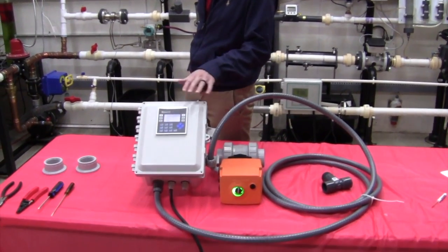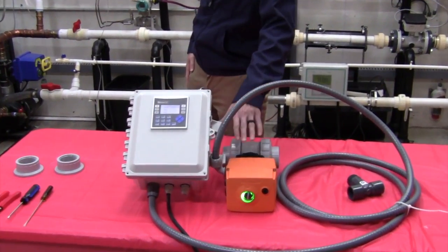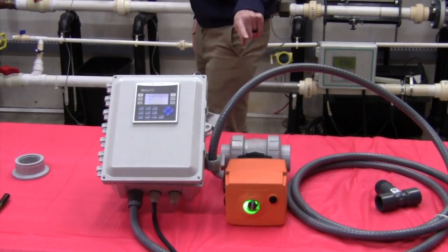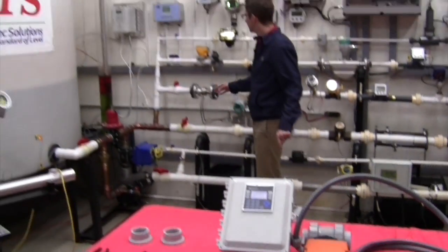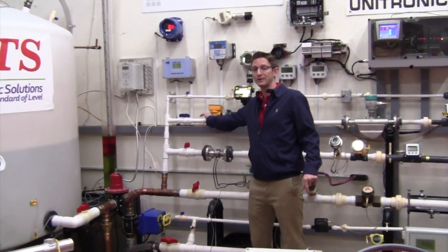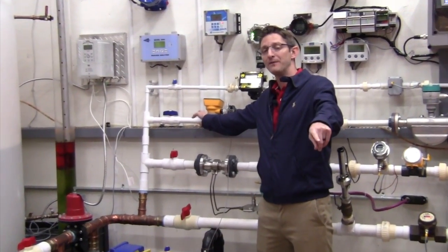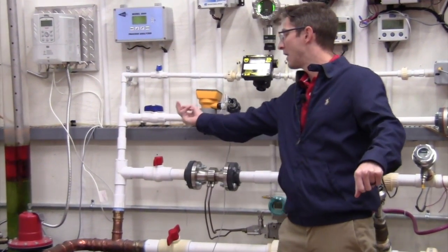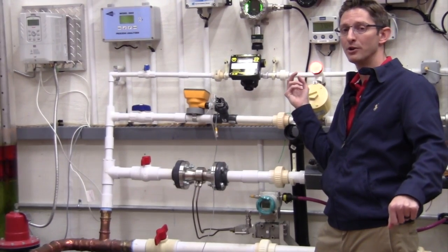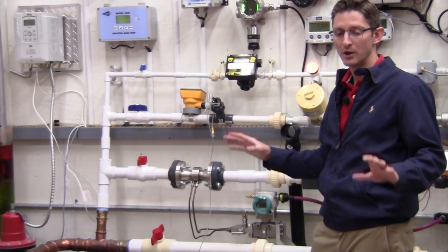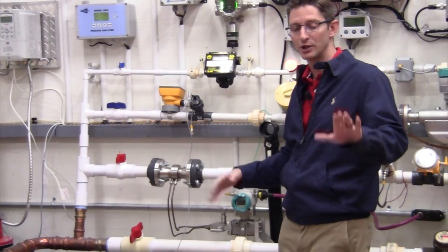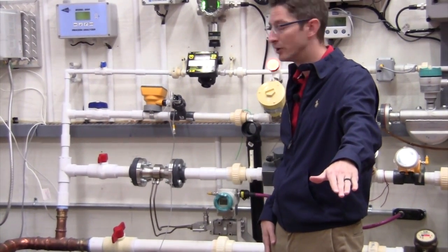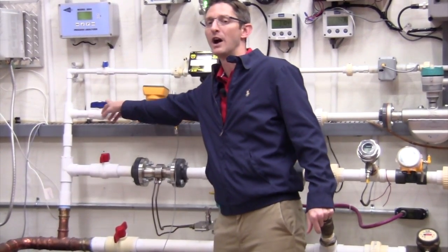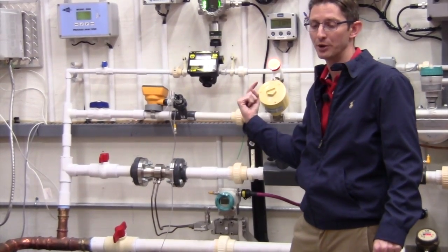What I'm going to do is put this into manual mode. I'm then going to open this valve. Typically that valve would be mounted upstream of this flow meter. So when I open that valve in manual mode, it will allow us to flow past the flow meter so we can do our calibration. But again, for the purposes of this demonstration, I'm going to show you the valve opening on the table. We have a manual hand valve here that allows us to flow past the flow meter.